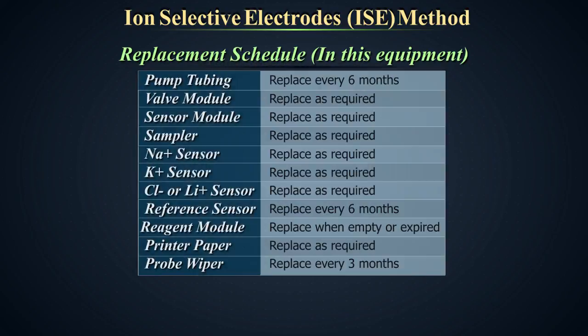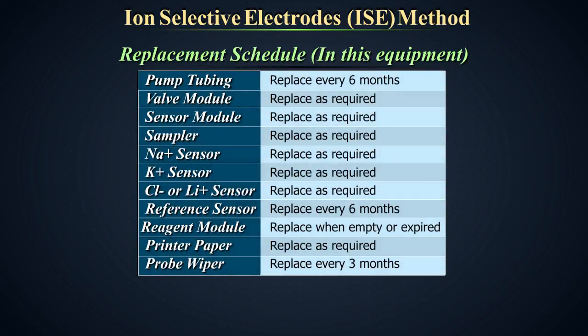Replacement schedule. The following schedule should be followed. Out of these, pump tubing, sensors, reagent and printer paper can be done by the technician. The rest should only be performed by the service person or engineer.